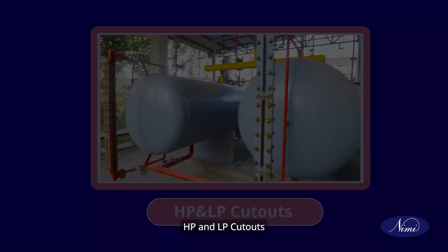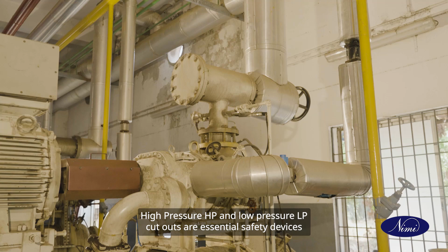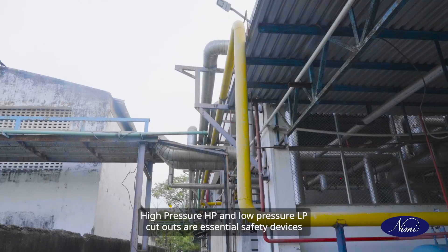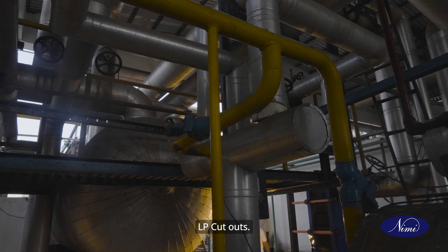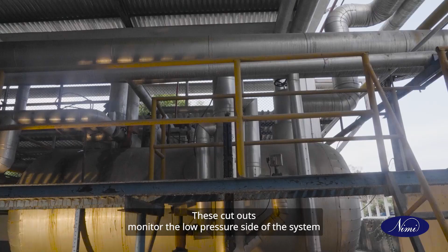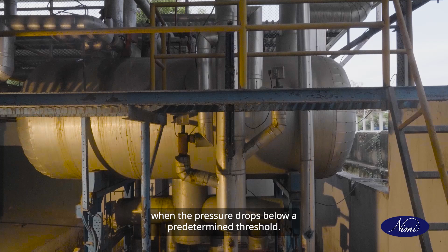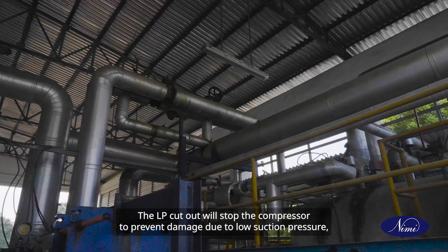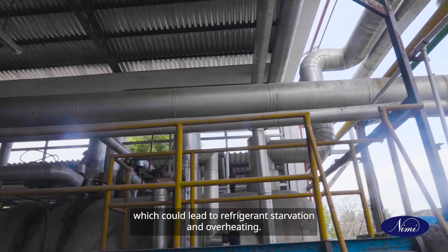HP and LP cutout. High pressure (HP) and low pressure (LP) cutouts are essential safety devices in the refrigeration system. LP cutouts. These cutouts monitor the low pressure side of the system. When the pressure drops below a predetermined threshold, the LP cutout will stop the compressor to prevent damage due to low suction pressure, which could lead to refrigerant starvation and overheating.